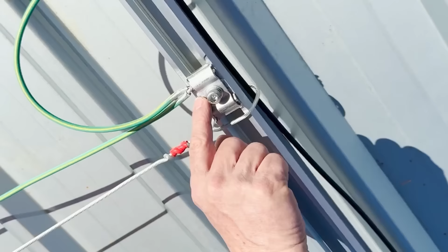Now I'll draw your attention to all the earthing as well. Notice the earthing here has been sprayed. They've used a silver Galmet spray, and that's just to protect the earth from corrosion, because remember this is copper. Now there is a Galmet on the market that is a green Galmet that some people use to distinguish between a standard Gal spray, say over a cable tray, and the actual earthing. But I think for the ease of the installer, having a standard colour is fine. There's no requirement for this to be a different colour.